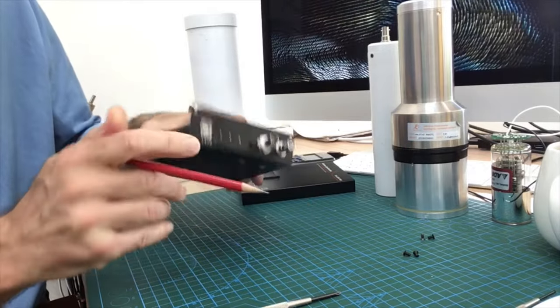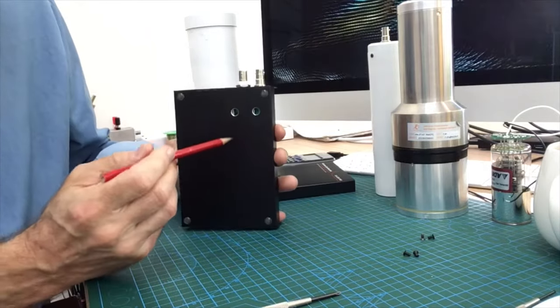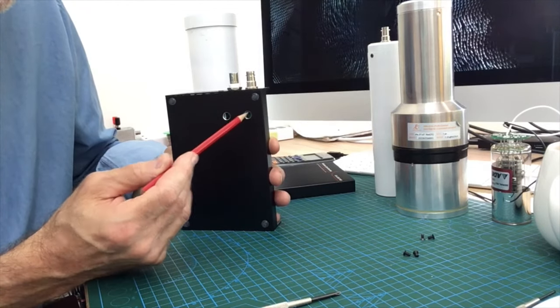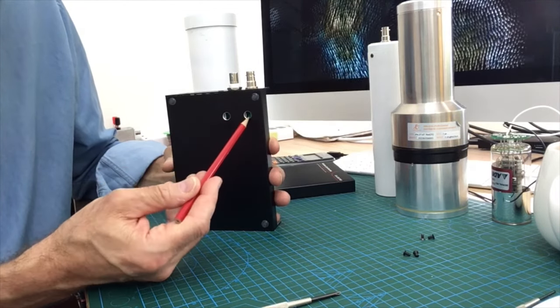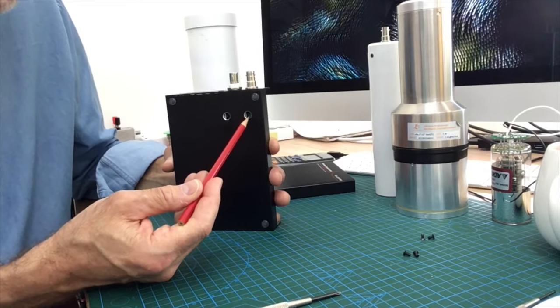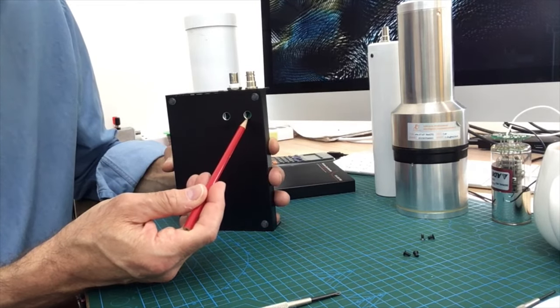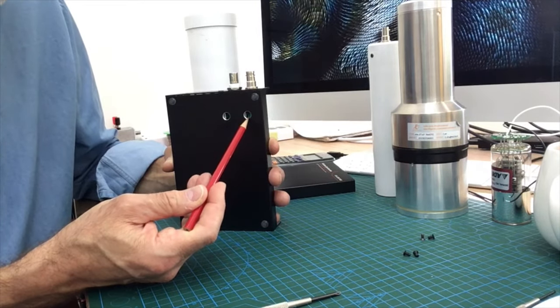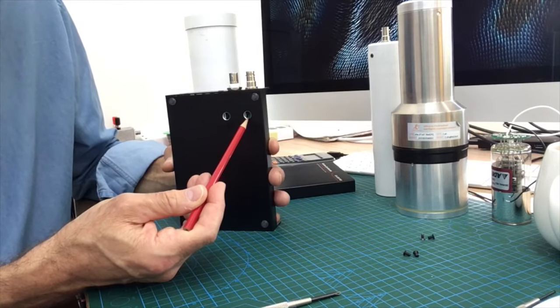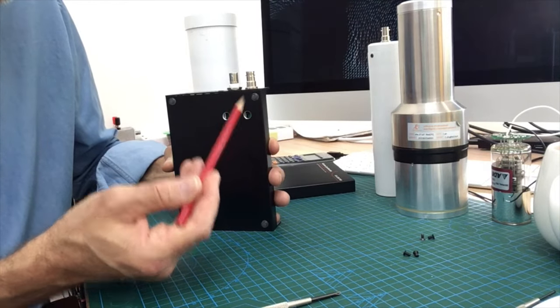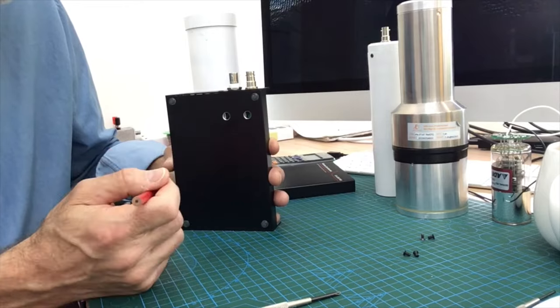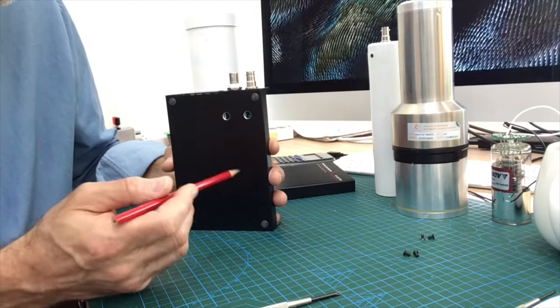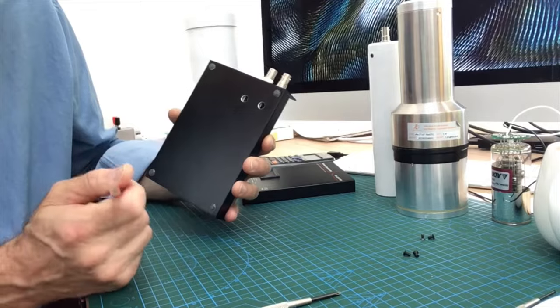And to facilitate that you'll find underneath the unit there are two little dip switches. Now this dip switch on the outside here sets the connection to be directly to the detector or via the coupling. So just keep that in mind if you're using a detector with two connectors, this switch needs to be in the down position.